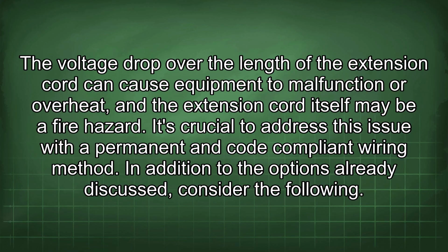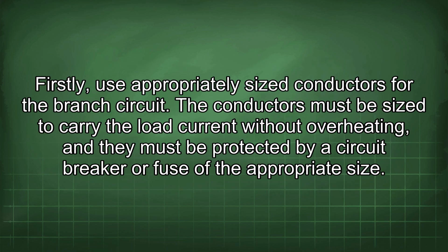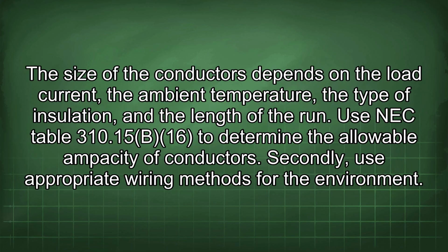In addition to the options already discussed, consider the following. Firstly, use appropriately sized conductors for the branch circuit. The conductors must be sized to carry the load current without overheating, and they must be protected by a circuit breaker or fuse of the appropriate size. The size of the conductors depends on the load current, the ambient temperature, the type of insulation, and the length of the run. Use NEC Table 310.15(B)(16) to determine the allowable ampacity of conductors.